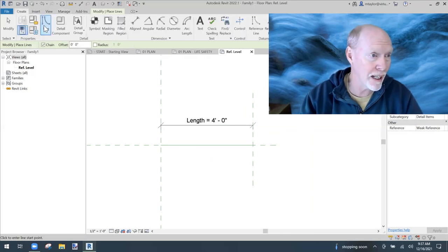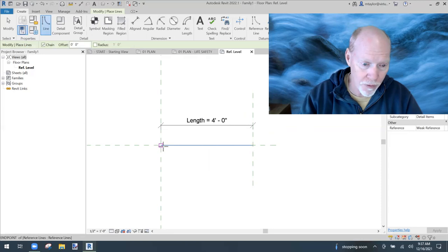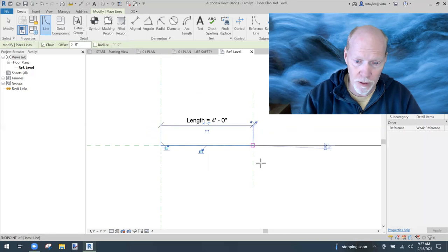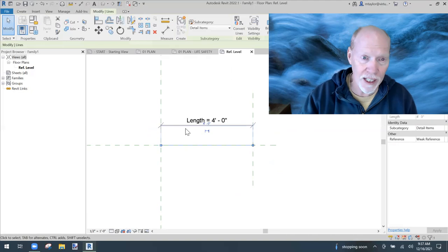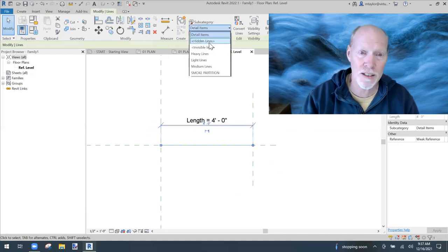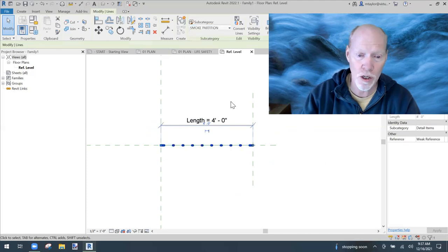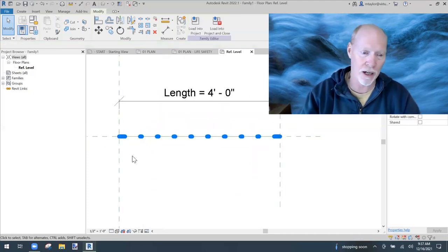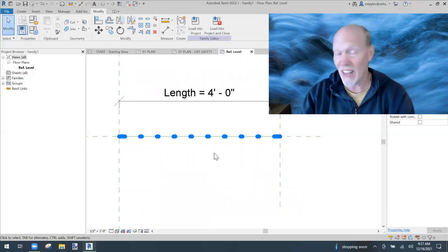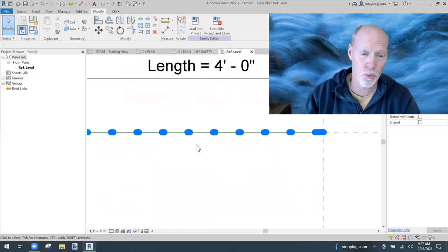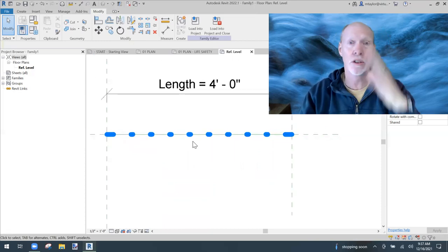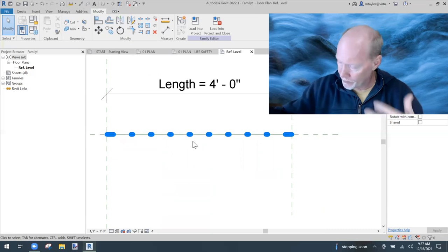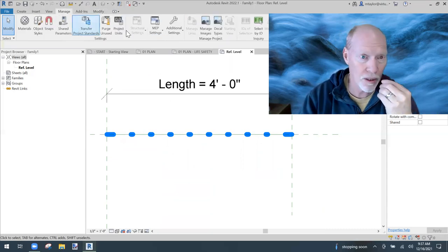Now I can draw a line with that subcategory. Go to Create, click Line, and draw from this intersection over to the other one. It seems like nothing happened — but if I highlight the line I just need to change the subcategory to Smoke Partition. There it is. If that's good enough, great — but personally I think the dots are too far apart, so let's fix that.